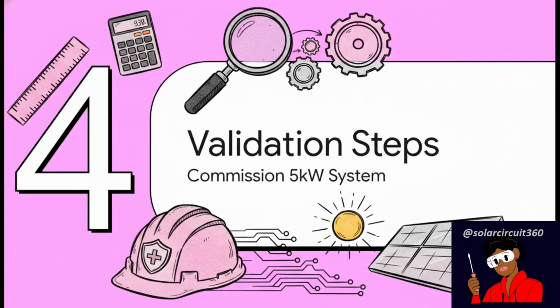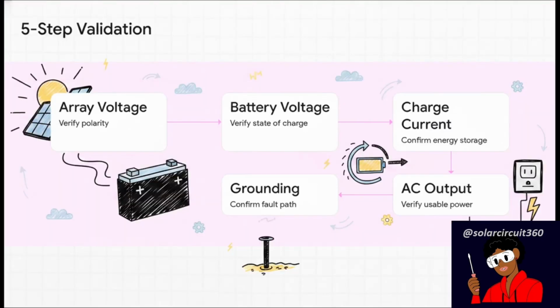Section 4. Step-by-step validation. Commissioning a 5 kilowatt system. Let's take that detective toolkit, our formulas, and our safety mindset, and apply them to a methodical, step-by-step validation of a 5 kilowatt system. Here is the exact 5-step investigative procedure that professionals use. We're literally mapping the journey of the power, starting up at the solar array, flowing down into the battery bank, verifying the charging current, testing the AC output of the inverter, and finally proving our safety net through ground continuity.